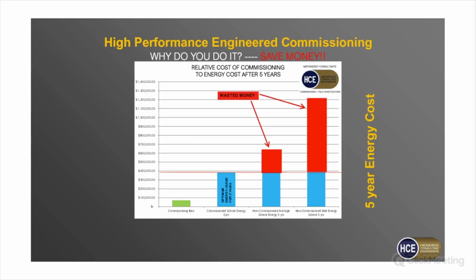What we've got here is a look at the typical cost for commissioning a standard elementary school versus the energy usage. You've got 4 different bar graphs. The blue represents the optimum energy usage over 5 years, what that cost might be, and the red represents potentially wasted energy if things aren't set up correctly. So you've got a couple of different scenarios. On average, in the middle, you could waste maybe $250,000 over 5 years. If you're one of the unlucky ones, like that other school, you could be wasting 100, 150, maybe more per year.